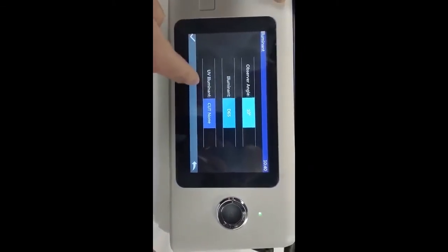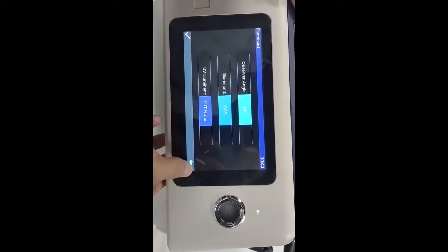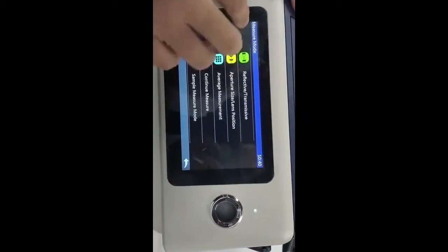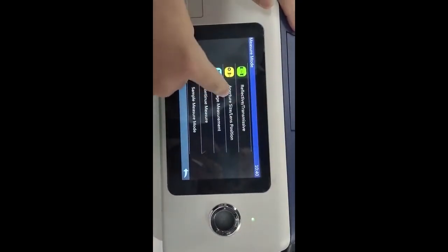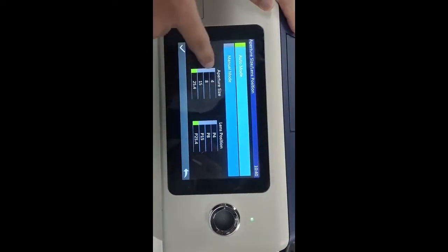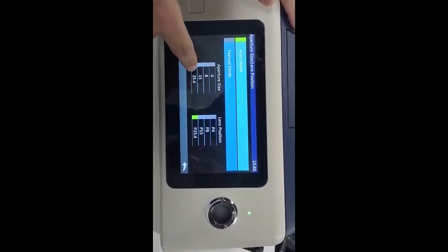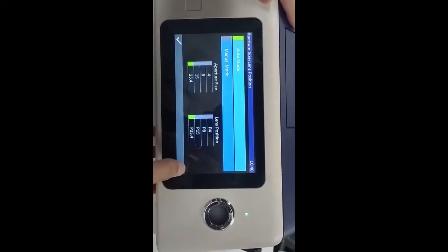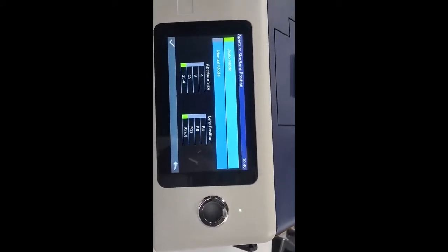Illuminant. You can choose the observer angle here and the illuminant, and if you want the UV illuminant. Measure mode. Measure mode is about reflective measurement and transmissive measurement, different measurement modes, and aperture size. There are four aperture sizes: 4mm, 8mm, 15mm, and 25.4mm. It's like this.